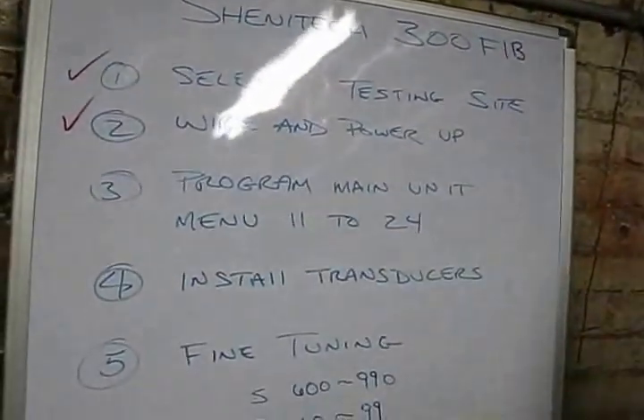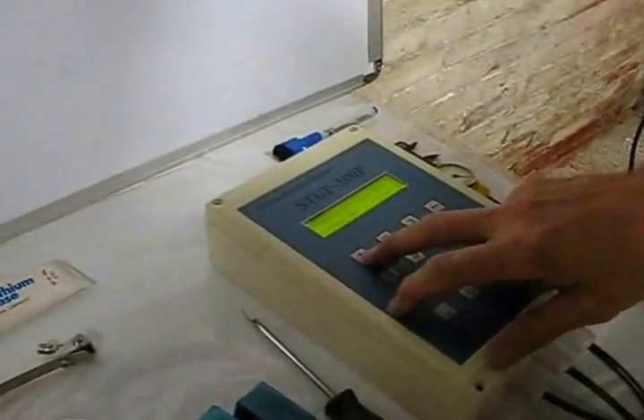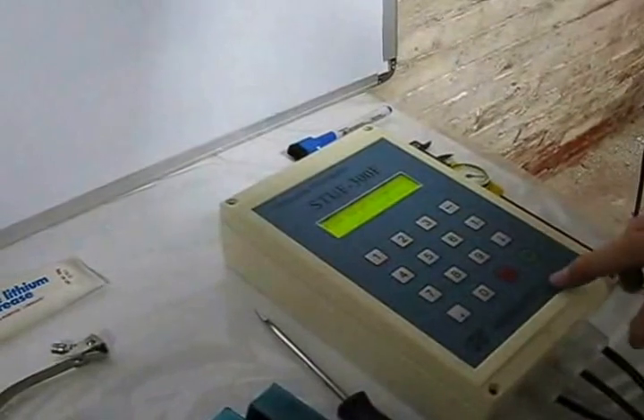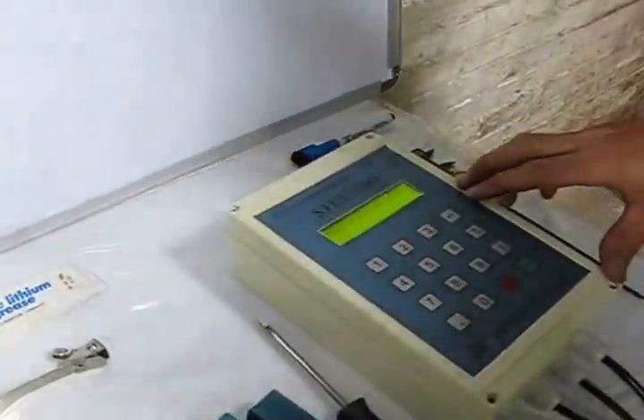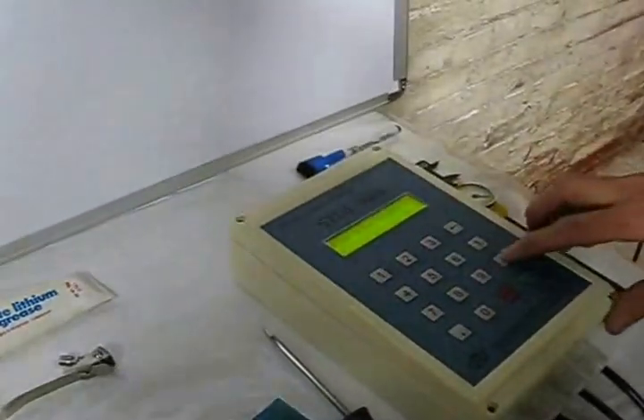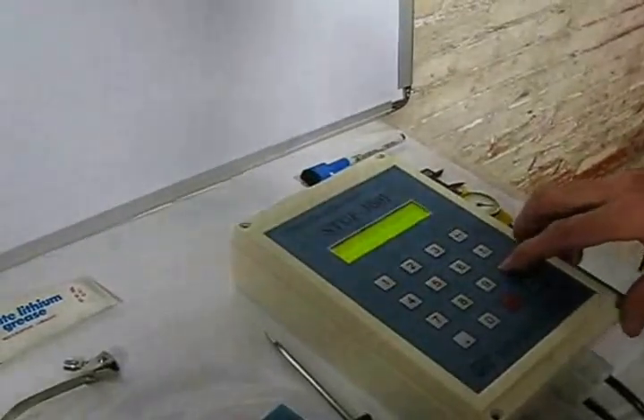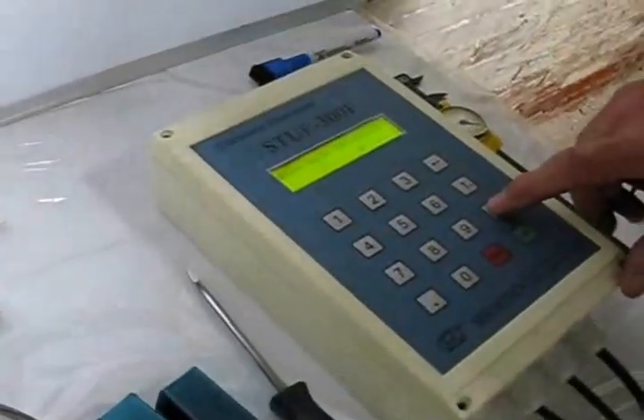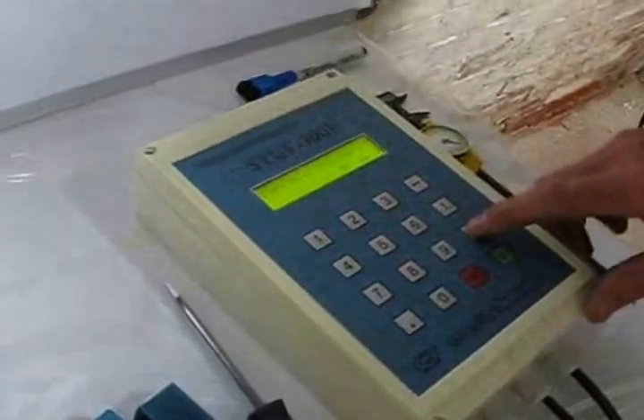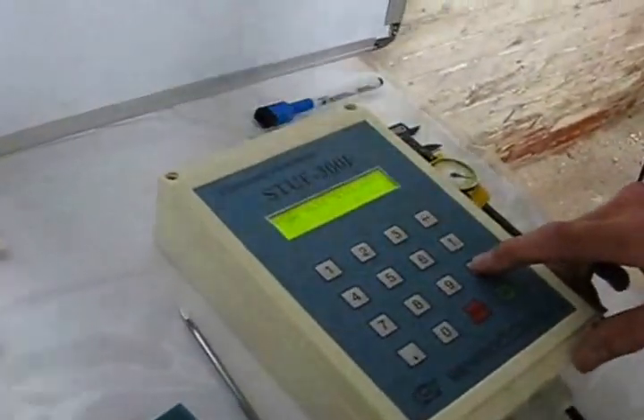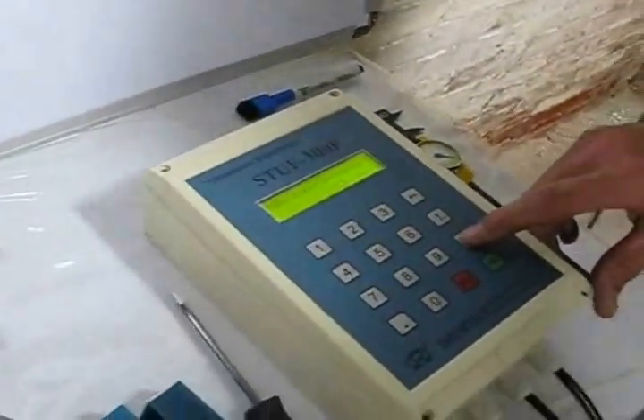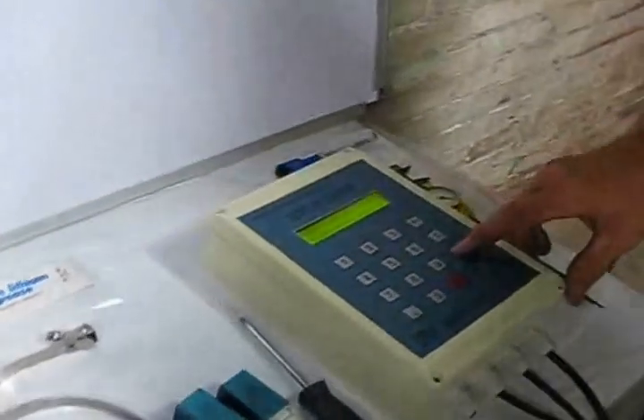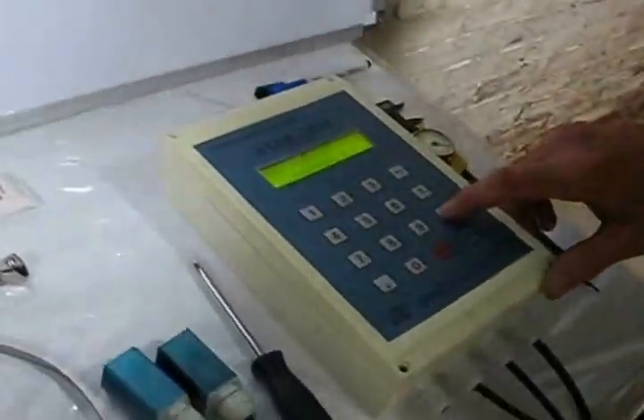We're going to program the main unit with menu 11 through 24. Hit menu 11, we hit enter. It gives us our pipe outer diameter. At this time we enter the pipe outer diameter. We proceed to the next menu. The next step will be to enter the pipe wall thickness. After the wall thickness is entered, we enter the pipe inner diameter. We enter the pipe material in the next menu.